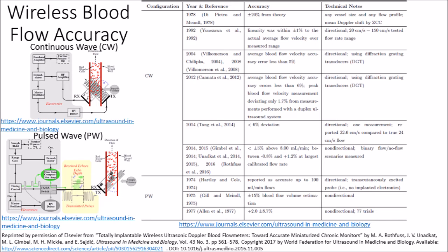The two Doppler blood flow monitor configurations found in literature use either the continuous wave Doppler principle or the pulse wave Doppler principle. Both continuous wave and pulse wave configurations can be designed to detect the direction of blood flow. Continuous wave Doppler devices are less complex than their pulse wave counterparts, but this reduced complexity comes at the cost of typically less accuracy. Continuous wave devices report the average spatial velocity across the entire vessel lumen, whereas the pulse wave Doppler devices can resolve the average spatial velocity in small increments across the vessel lumen. Directional flow measurement devices are generally more accurate than non-directional devices and are particularly useful when the blood flow profile is either unknown or known to be turbulent, such as in the arteries.